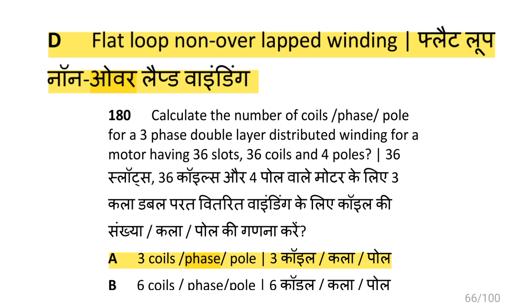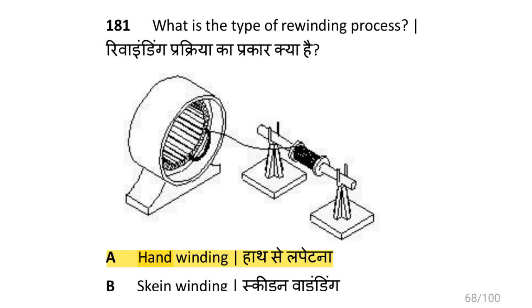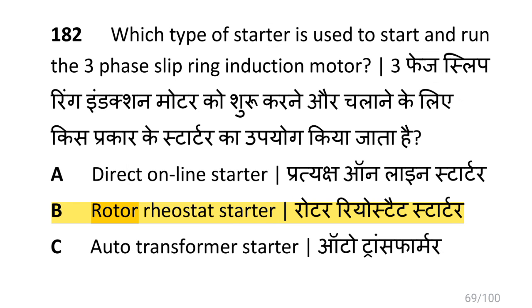Calculate the number of coils per phase per pole for a three phase double layer distributed winding for a motor having 36 slots, 36 coils, and 4 poles: the answer is three coils per phase per pole. The type of rewinding process illustrated is hand winding. The starter used to start and run a three phase slip ring induction motor is the rotor rheostat starter.